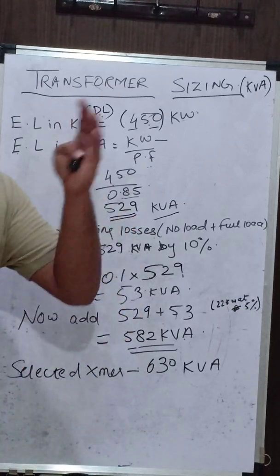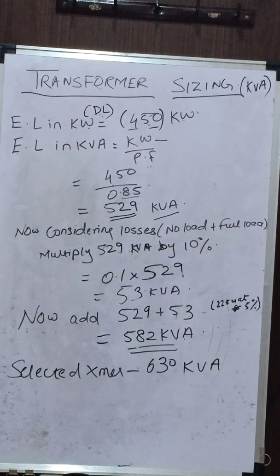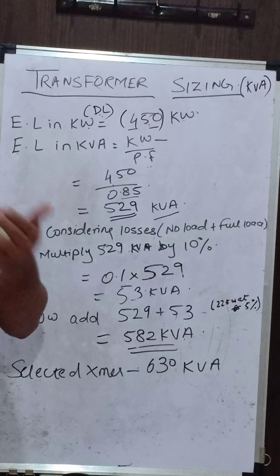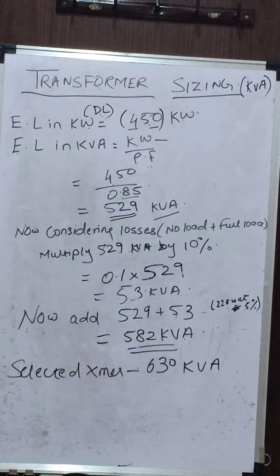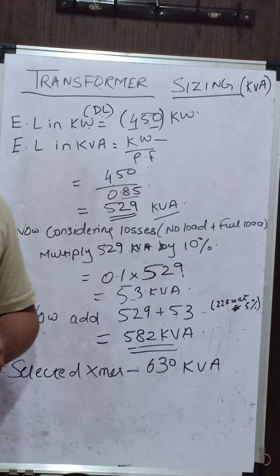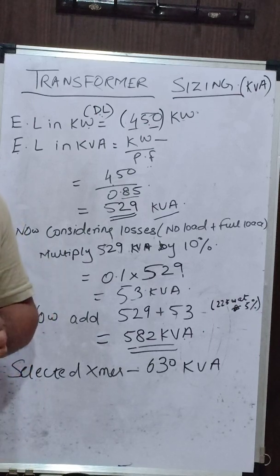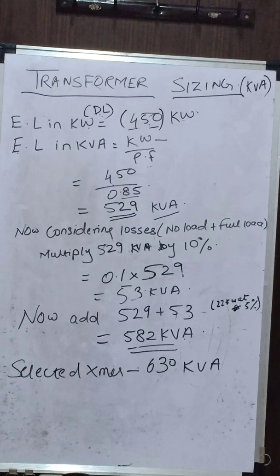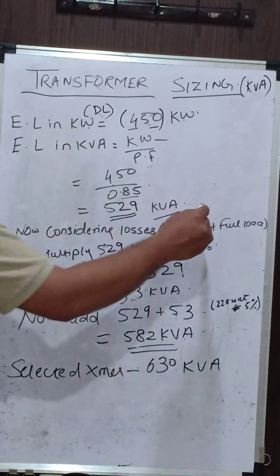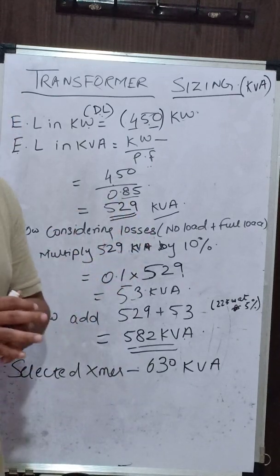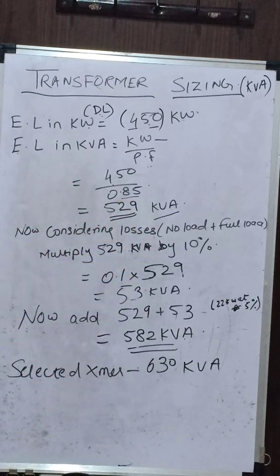Now, if you want to select a transformer, you cannot select one of exactly 529 kVA. This is because there are many losses taking place inside the transformer. These losses include no-load losses — hysteresis and eddy current losses — and full-load losses, which are copper losses. Because of these losses, if you supply 529 kVA at the transformer input, the output may only be around 500 kVA, meaning 29 kVA is wasted as losses. That is why you cannot size the transformer exactly based on the electrical load.